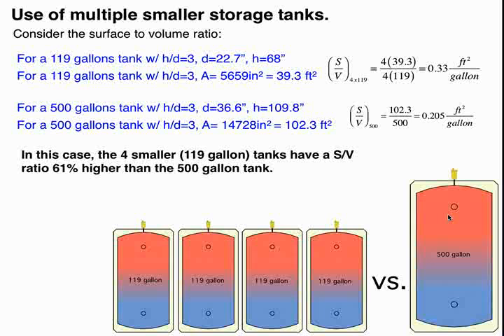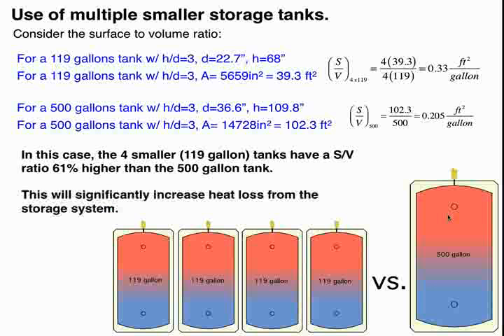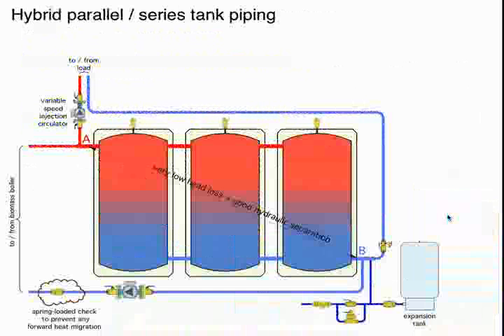Well, obviously access. You may not be able to get a 500-gallon tank through, let's say, a 36-inch wide door in an existing mechanical room, or into an elevator or down a stairs or something like this. You'd have to go to the smaller tanks. But when you don't have the spatial constraints or the logistic constraints of moving the tank in, generally speaking, larger tanks are going to have better surface to volume ratios than smaller tanks are.